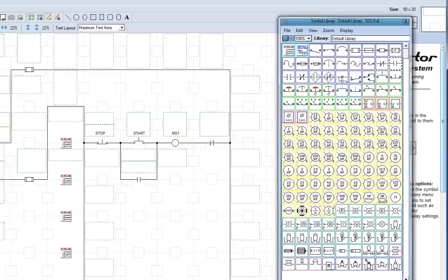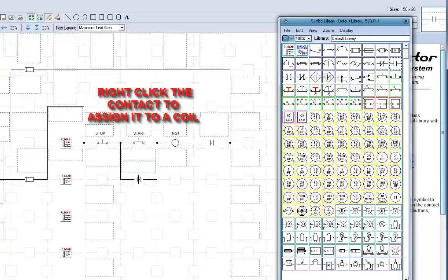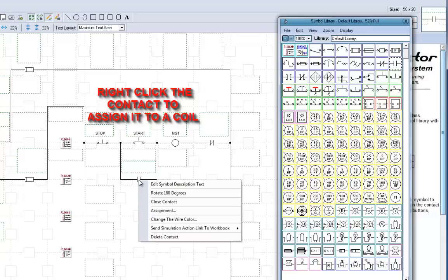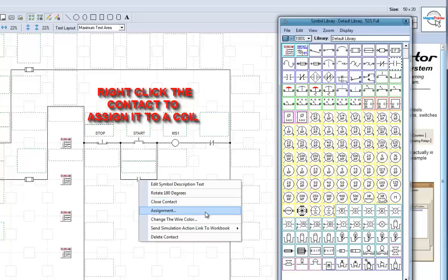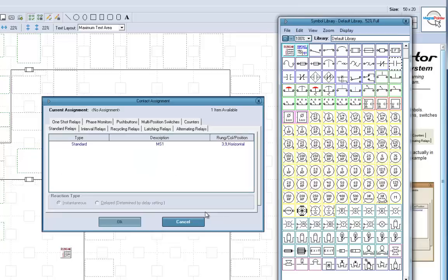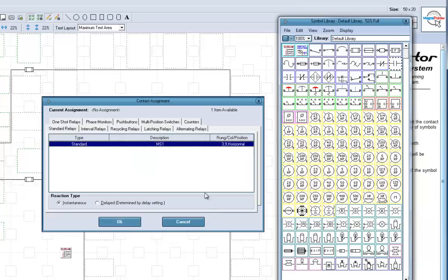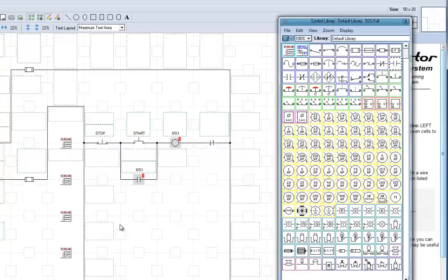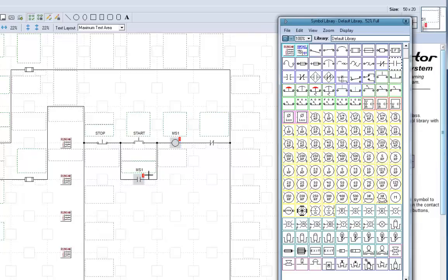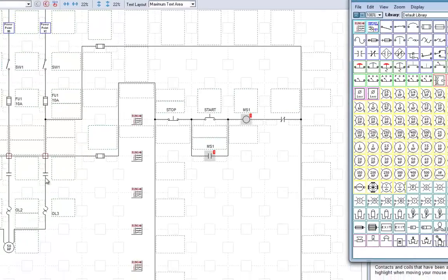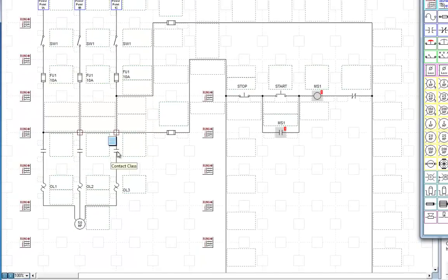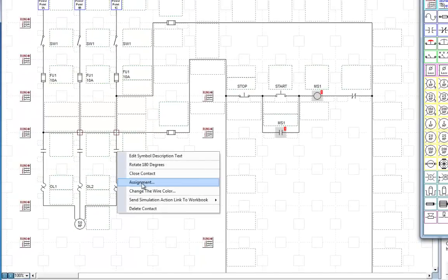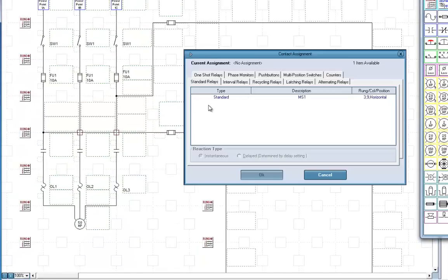So before I type anything here, I'm going to right click on it and select Assignment. And select it to the coil that's there. Standard Relay Coil, MS1. You can see now that they're connected together assignment-wise. Let's do the same thing over here. Assignment, MS1. Assignment, MS1.